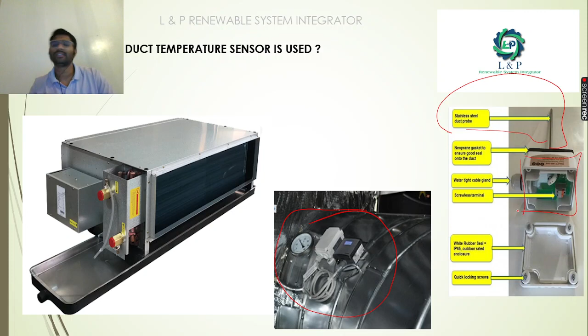There are so many models available in the market. Now let us see a simple example of the Greystone. As you can see here, this is the sensor wiring, and the probe is connected here. Most importantly, if you want to convert the temperature to the required output, for example a milliamps current or a 0 to 10 volt DC, it depends on the sensor that you choose, because now we have a sensor which produces an output of 4 to 20 milliamps, so it's in the milliamps range.